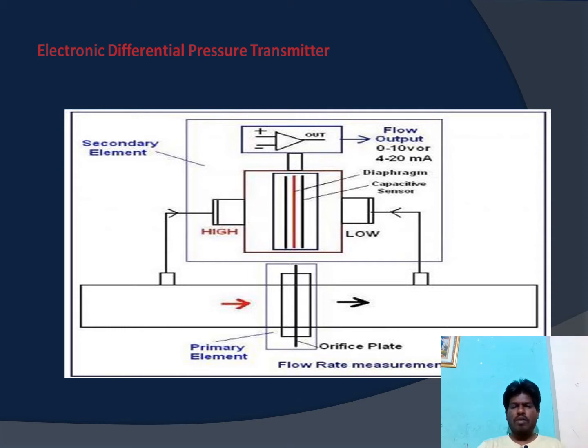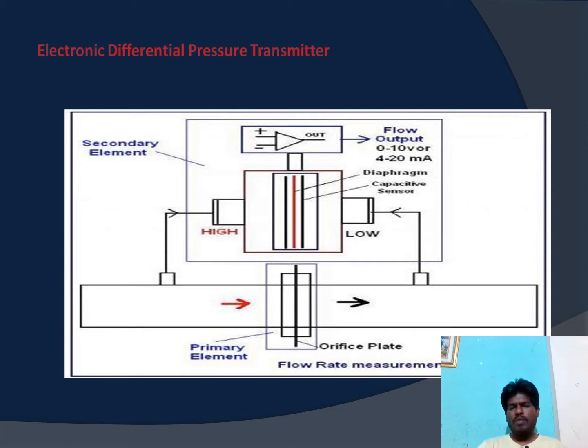The function of any electronic transmitter is that it gives the output in a standard signal, that is 4 to 20 milliampere. For that, there are basically two sections: one is for the sensing and the second is for the signal conditioning system. Here I am particularly talking about the DP cell, also called a differential pressure transmitter.